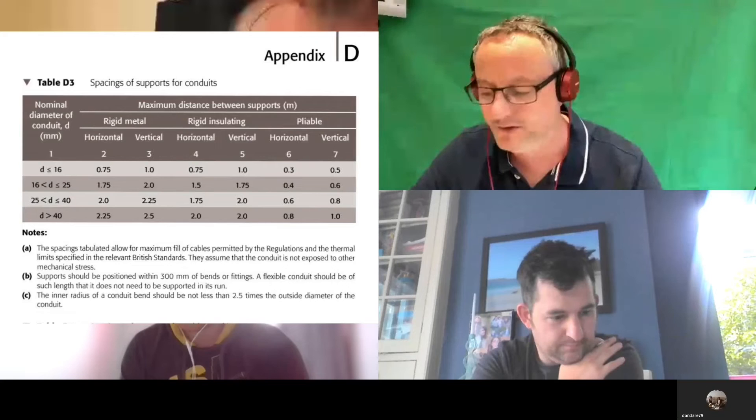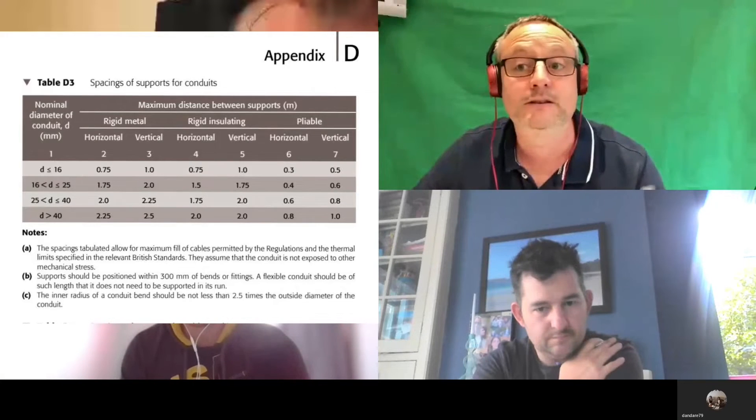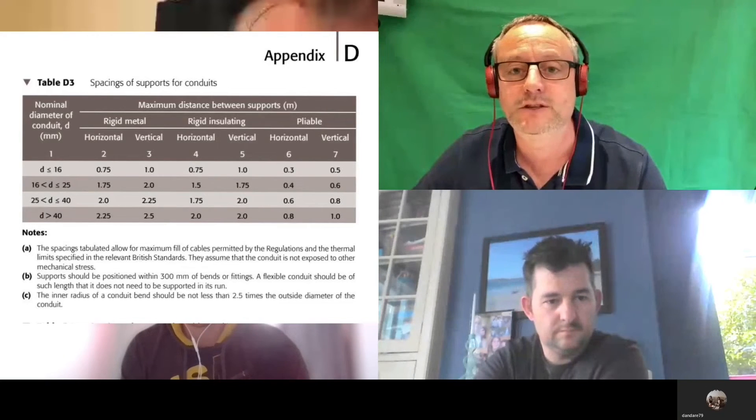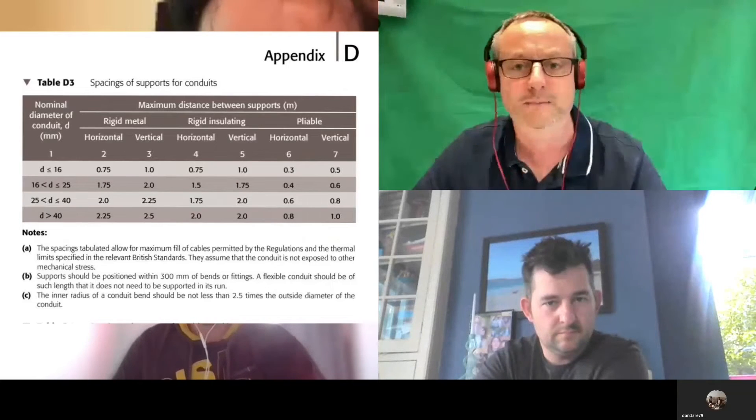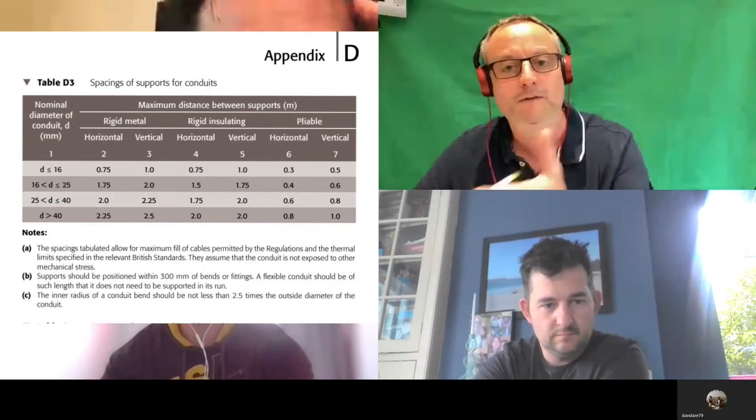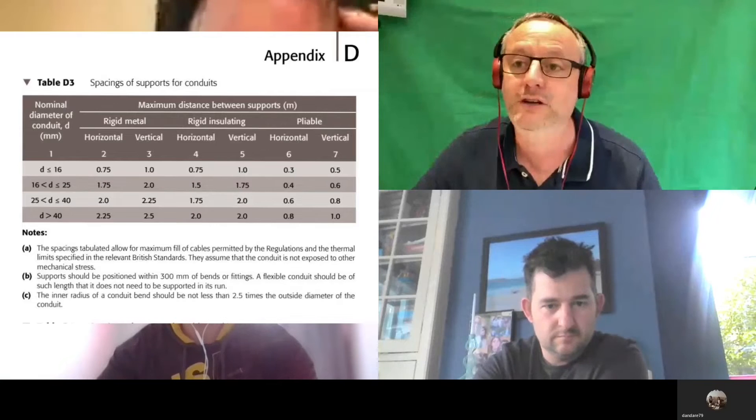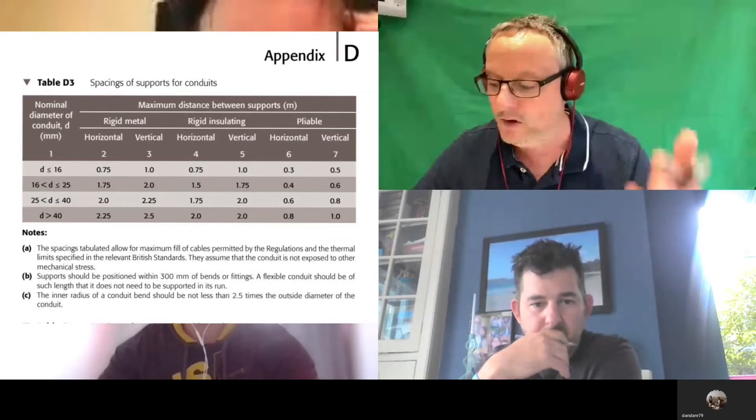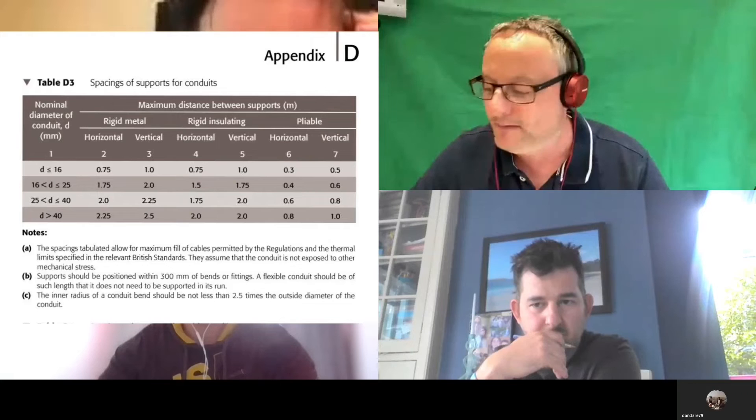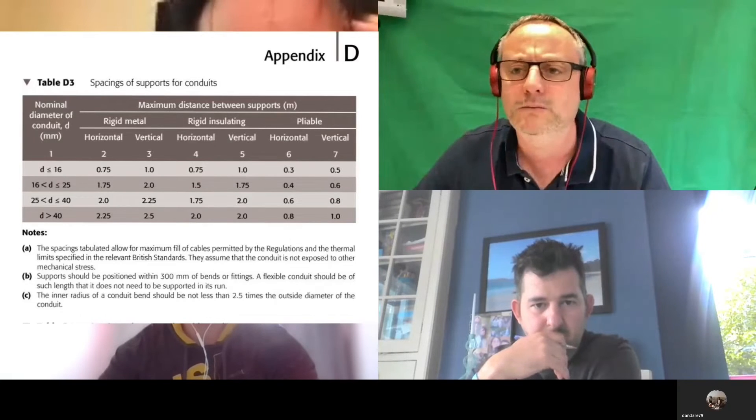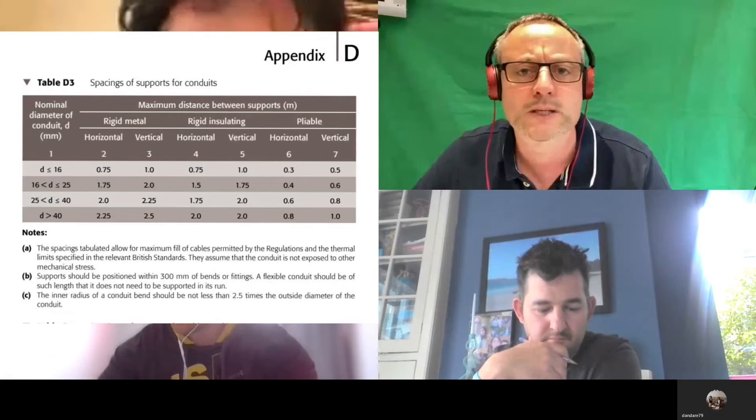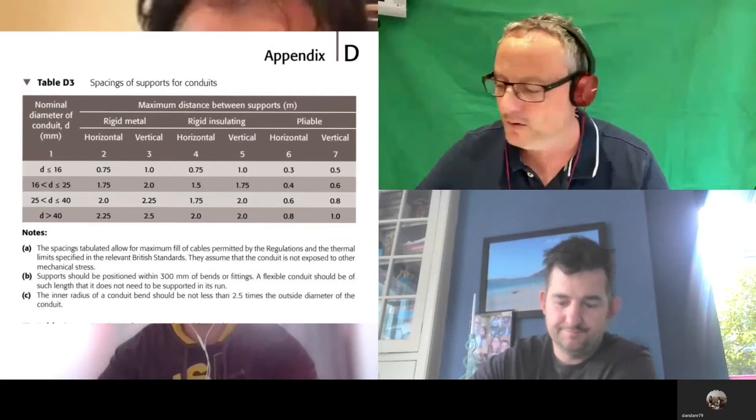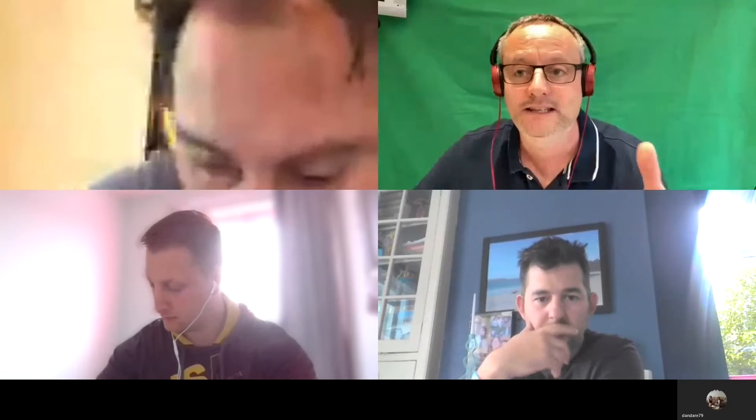As you look down each of the columns, whether you're in metal or plastic, as you work down them and increase the size of the conduit, we actually increase the spacings between our fixings. It's not counterintuitive, but in your own mind you might think you'd have to clip it more often, but actually it's self-supporting, it's a little bit more rigid. The last column says pliable. What do we mean by the word pliable? Flexible.